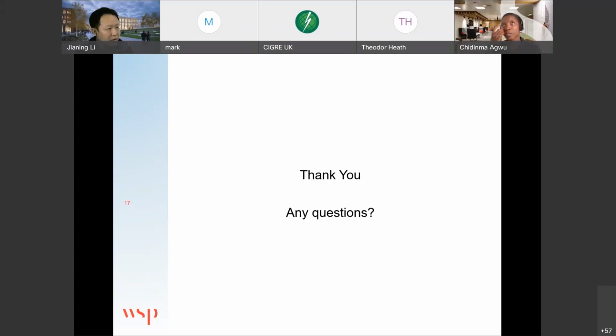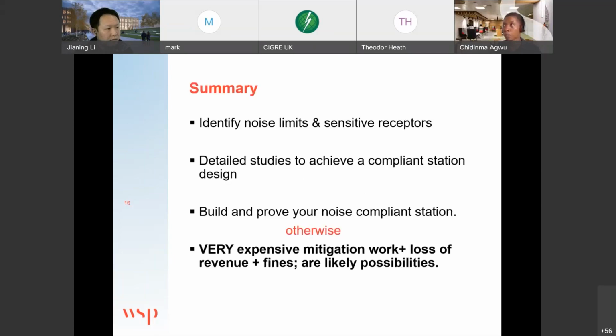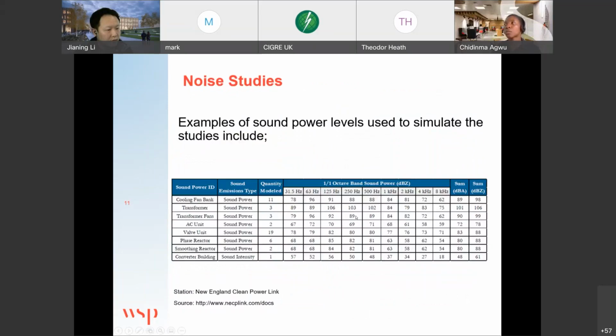I'm not sure about high frequency, but one issue you sometimes have with converter stations, especially LCC converter stations, is that the transformers, because of the harmonics, can be subject to tonality. What that means is that you might have just one specific octave band where the noise is quite high, almost like a pitch. I'm not sure about smaller electrical items, but with converter stations, having that specific pitch within one band or a very narrow spectrum is an issue referred to as tonality.